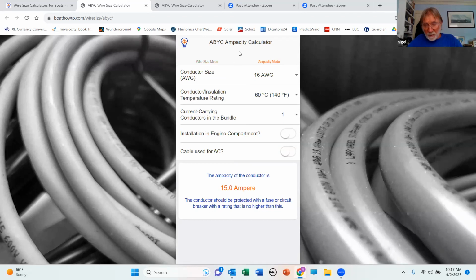Let's say we already have in the boat some conductors. And incidentally, all of these conductors should have their insulation labeled with the size of the conductor and the temperature rating of the insulation. If they're not labeled, then they're not standards compliant. Now, some European boats don't use labeled conductors, at which point when the boats are imported into the US, a sharp-eyed surveyor could look at that and could require the whole boat to be rewired, because you have no idea without getting a micrometer out what the size of the conductor is. And even then you don't know what the temperature rating of the insulation is. So it's all got to be labeled.